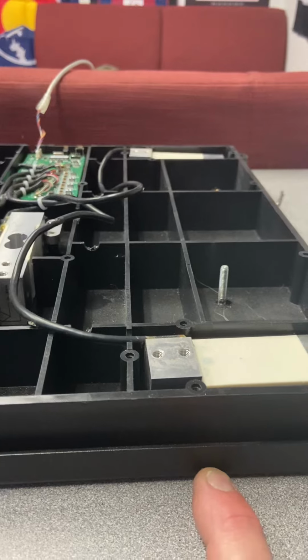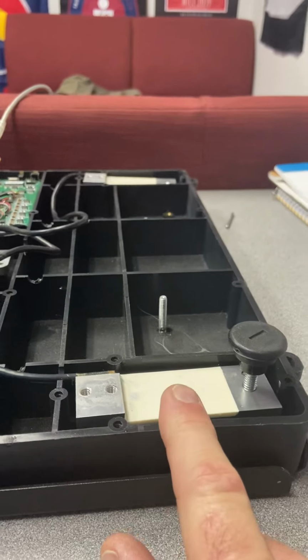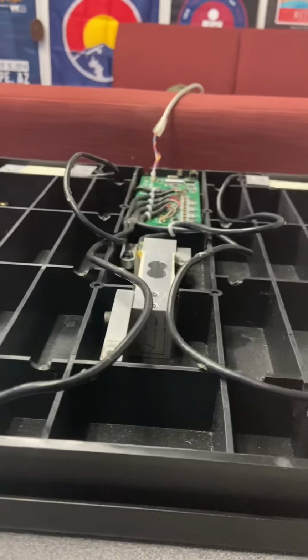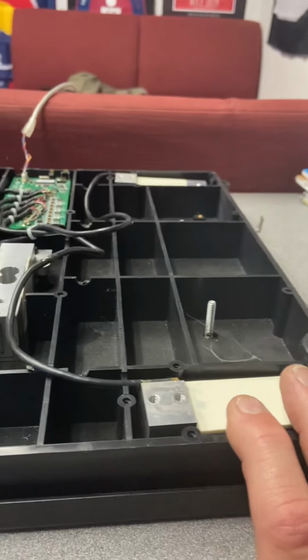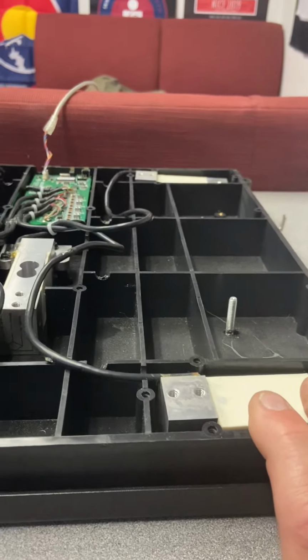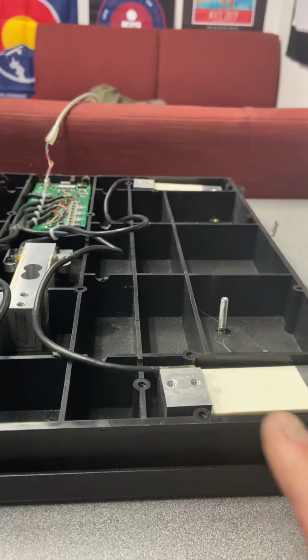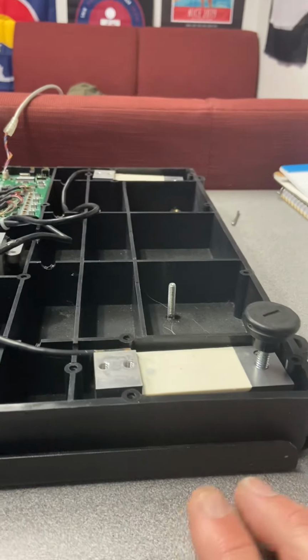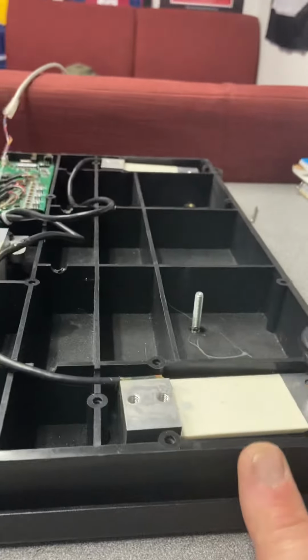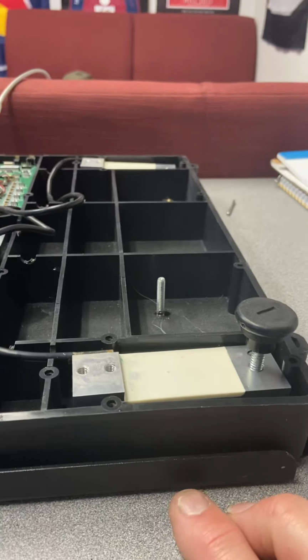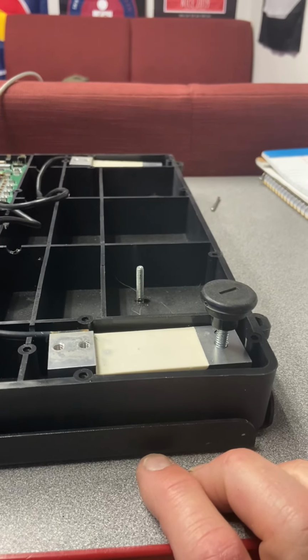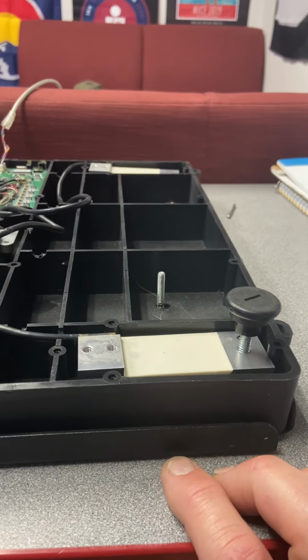You want this level so that all these force transducers are measuring vertical force. If it's not level, it's not measuring vertical force, it's measuring the normal force, normal to the surface. You may want to do that — you could put this on a ramp and measure the force normal or perpendicular to the surface.